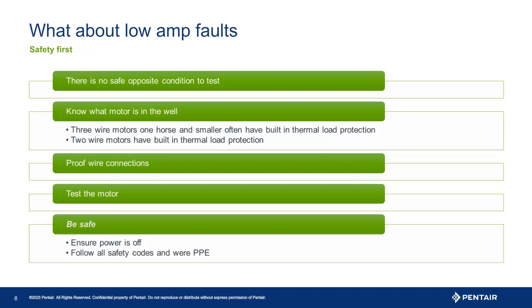Well, first remember, if the motor is a 1 horsepower or smaller 3-wire pump, there may be a thermal overload that is tripped and may take up to 15 minutes or so to reset. This is important to remember when measuring ohms while evaluating the windings. Should you not get a reading, wait and remeasure. Also note that any 2-wire motor will have a thermal overload.